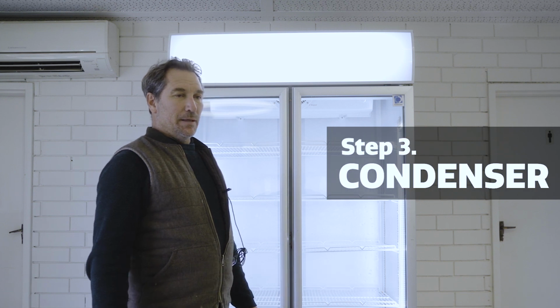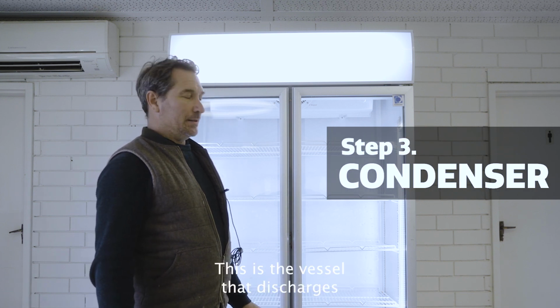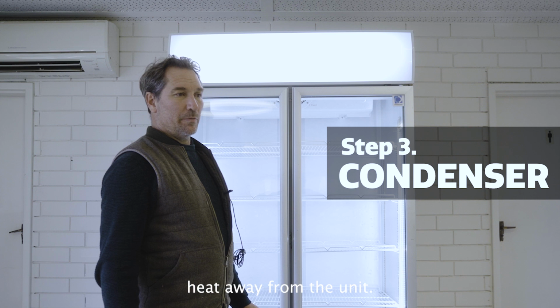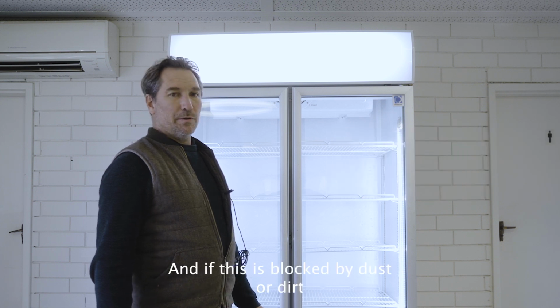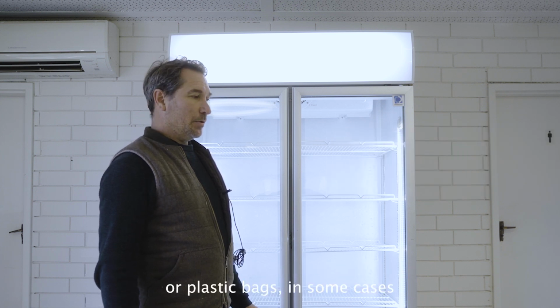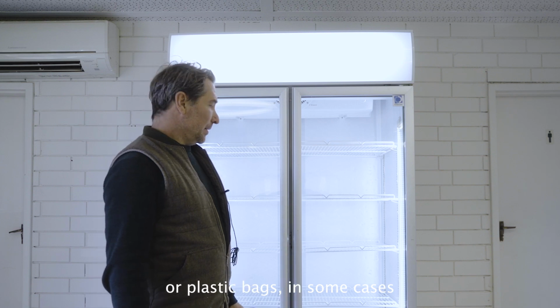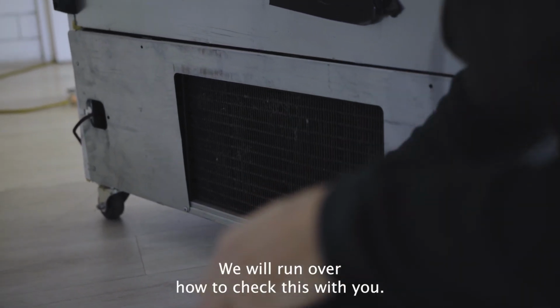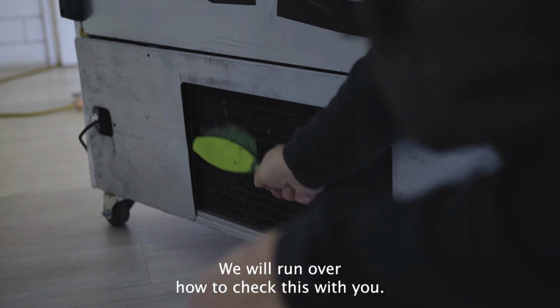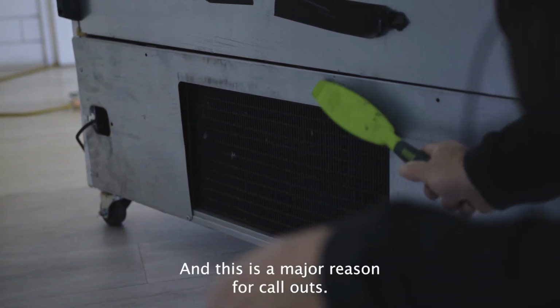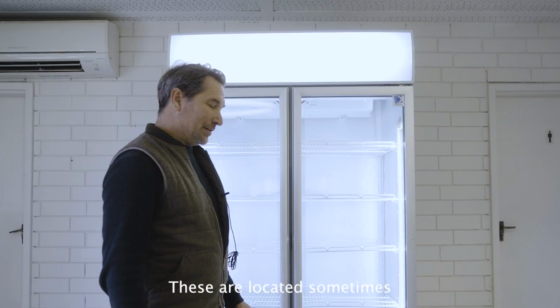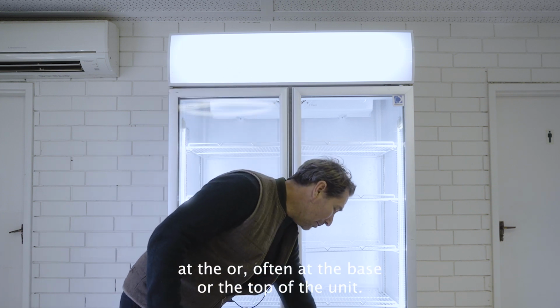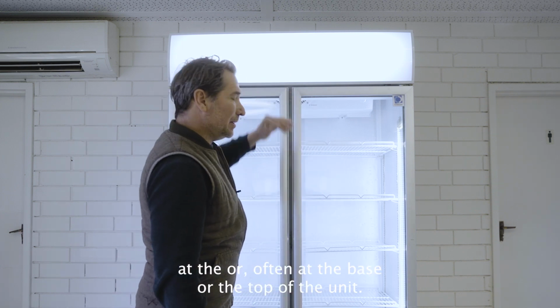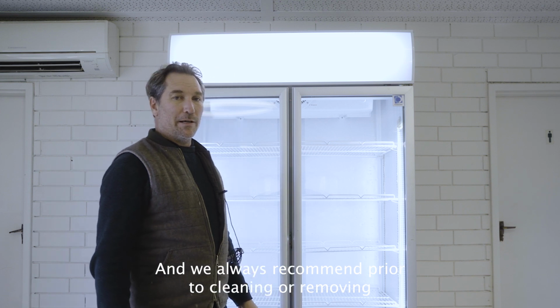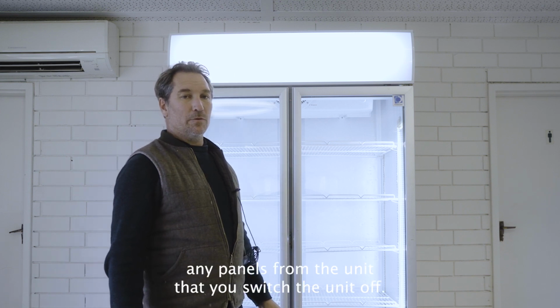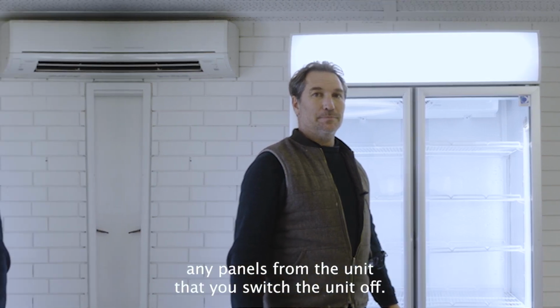So our main call out and a major service point for any fridge or freezer is the condenser. This is the vessel that discharges heat away from the unit. And if this is blocked by dust or dirt or plastic bags in some cases, it'll stop the unit from cooling. We'll run over how to check this with you. And this is a major reason for call outs. These are located sometimes or often at the base or the top of the unit. And we always recommend prior to cleaning or removing any panels from the unit that you switch the unit off.